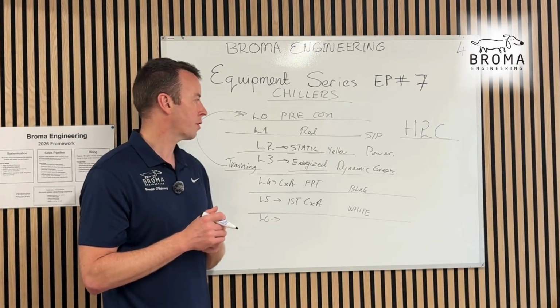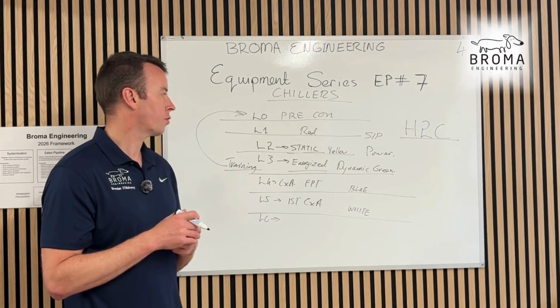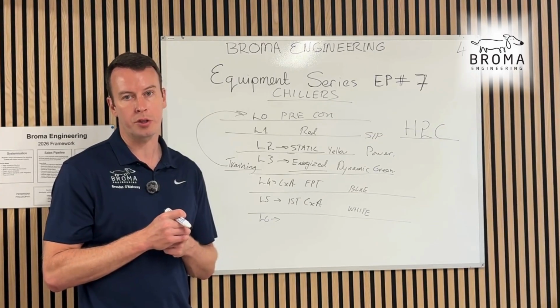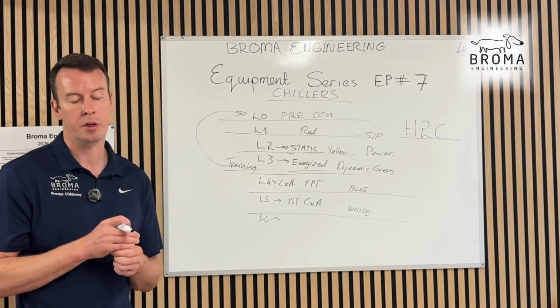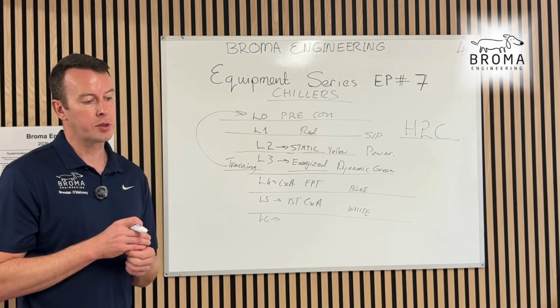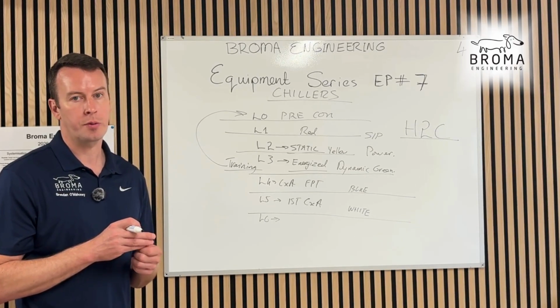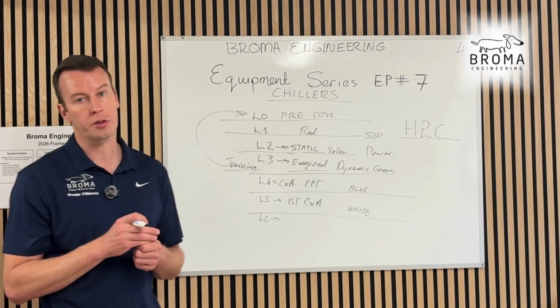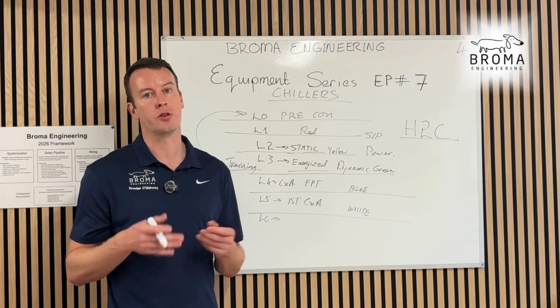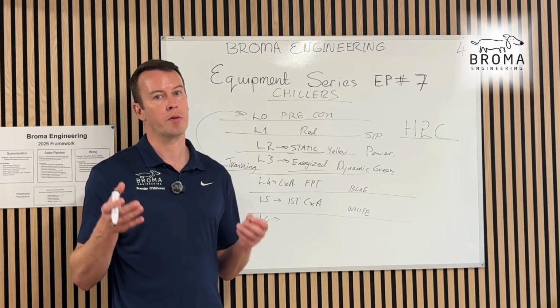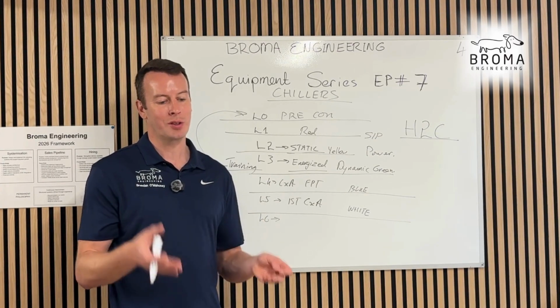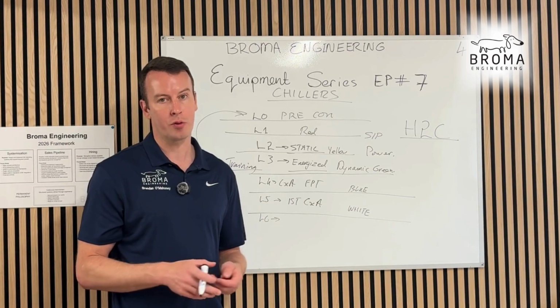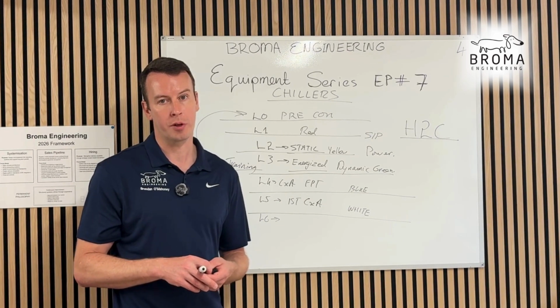You could drill the holes on site with a mag drill, or you could drill them in the fabrication yard before the steel gets to site. Depends on the circumstances, sometimes one's easier than the other. It depends on the risk, it depends on how much you can adjust the steel and all these kinds of things. It's a judgment call. But remember, when that chiller comes, you want it to land properly and you want to be able to bolt it up quickly and move on with the rest of your life.